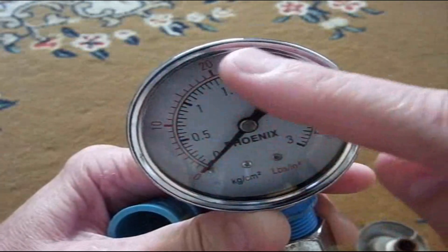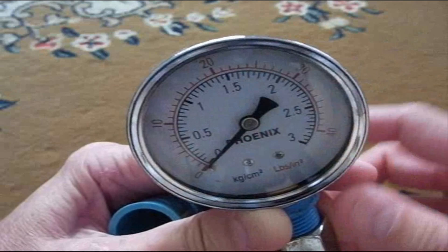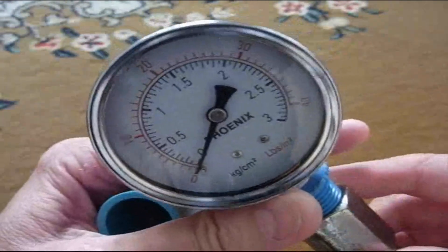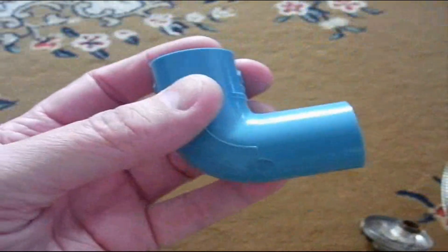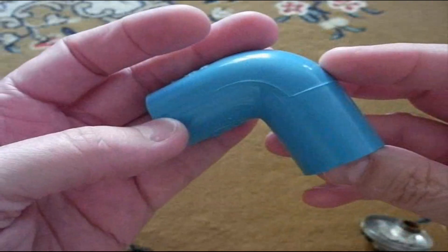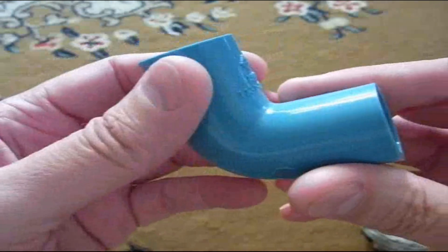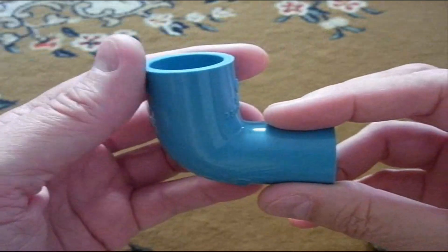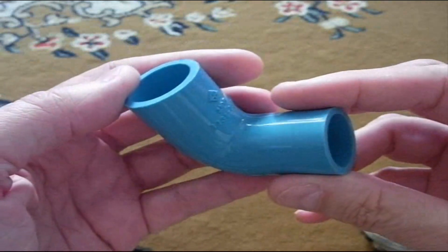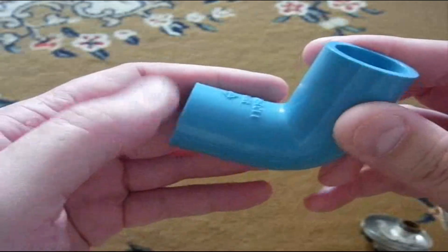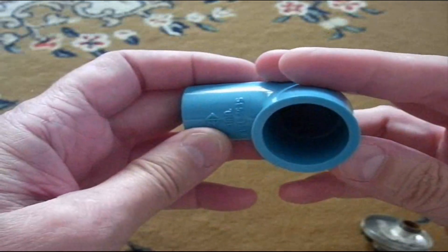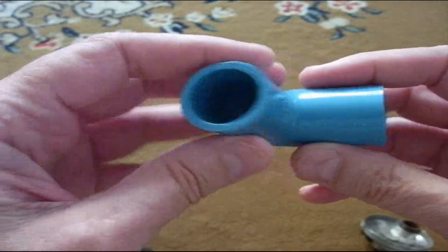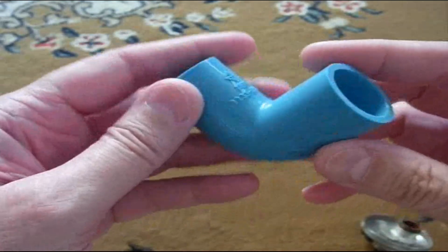So what is the difference between the static pressure and dynamic pressure? What does that tell us? Well, in one case I found I had 15 of these in a very short distance and it was killing the water pressure. I understand that these increase friction by about 1.5 to 1.7 percent each. So 10 of them is like 17 percent loss in your pressure, your flow. So that's pretty significant.